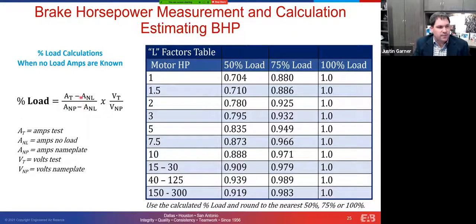And to do that, we're going to have our operating or test amps. This is our average amperage that we measure, our nameplate amperage, and then our no load amperage. And you're going to say, where do I find my no load amperage? Well, I'm going to show you that on the next slide. That's something that the manufacturer does publish for the motor. So you might have to go look it up if you're concerned about that. I guess you could, if you have the ability to unhook the motor and run it with nothing connected to it, you could get it that way. But this is normally not on the nameplate. So you may have to do a little extra work to get this value. Same thing here. This is your test voltage and your nameplate voltage, like we talked about earlier.